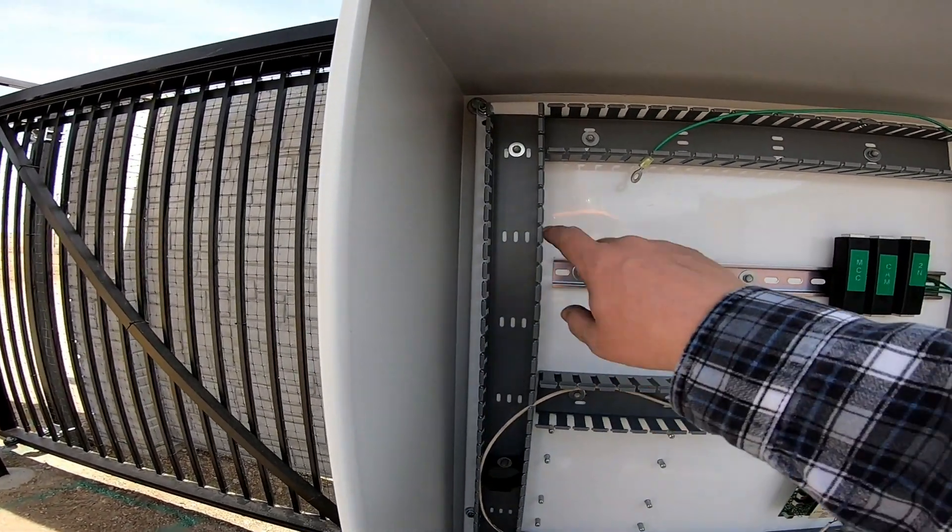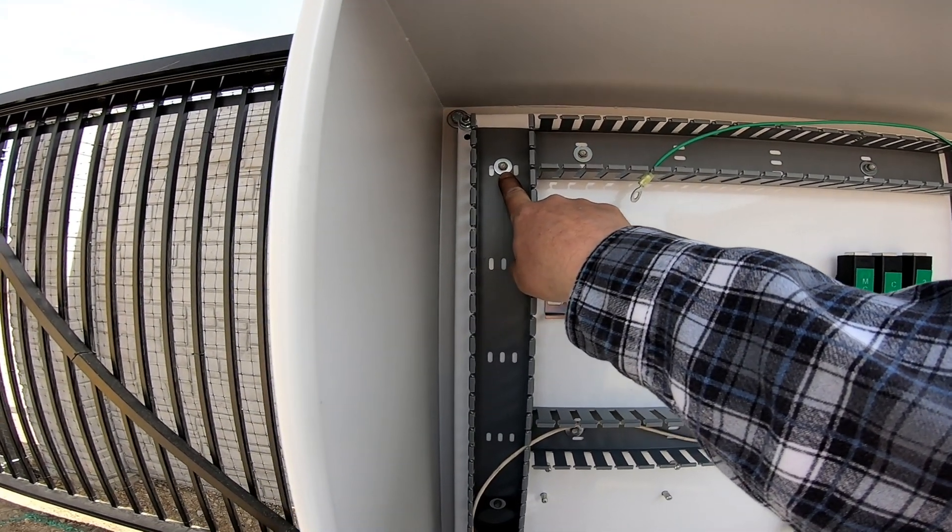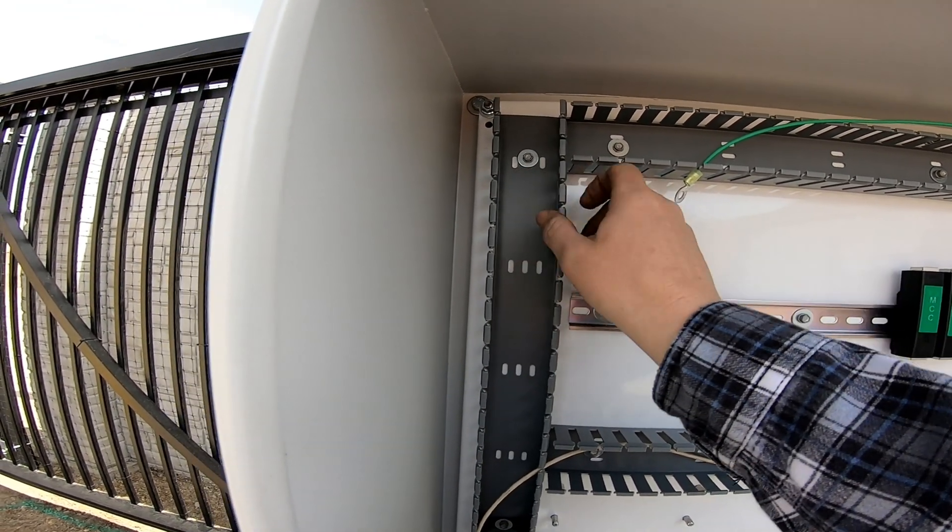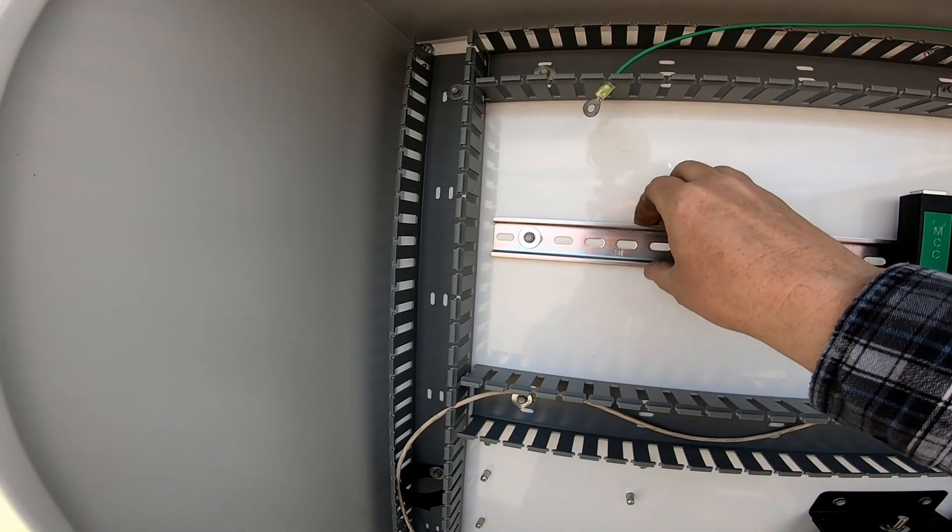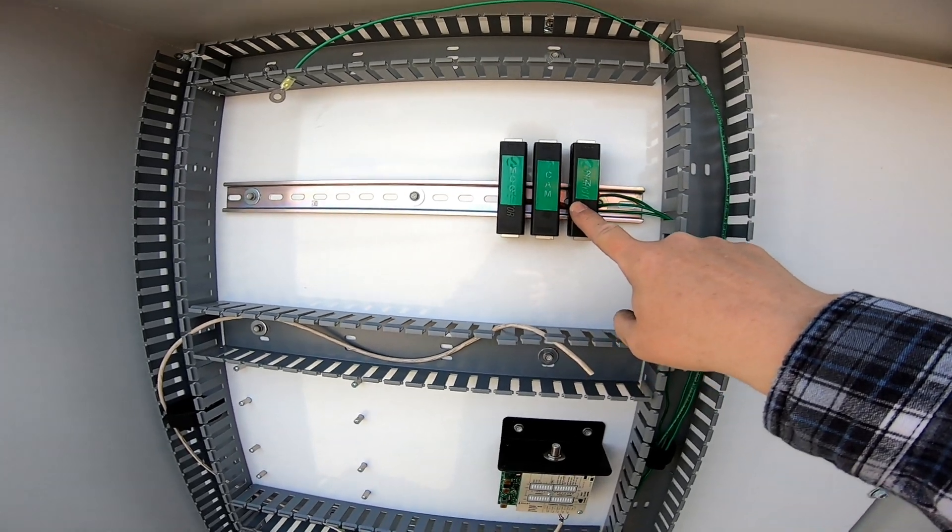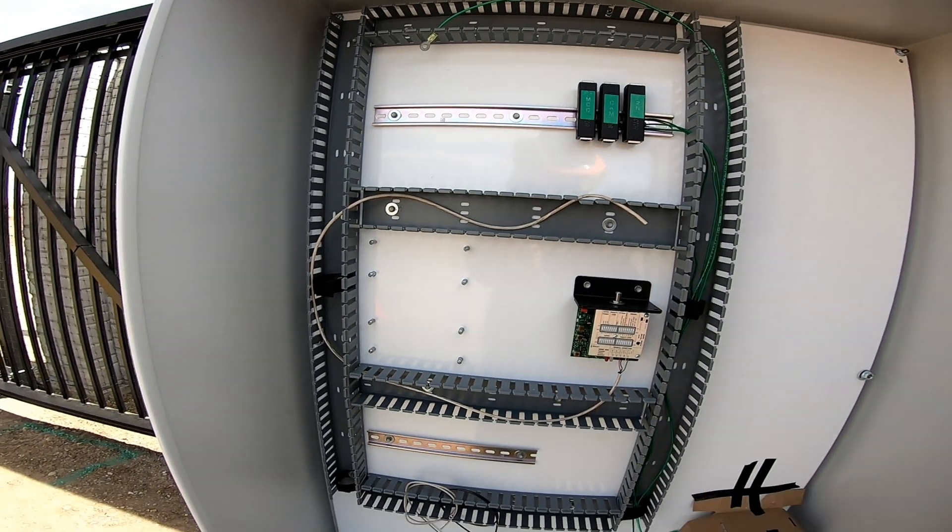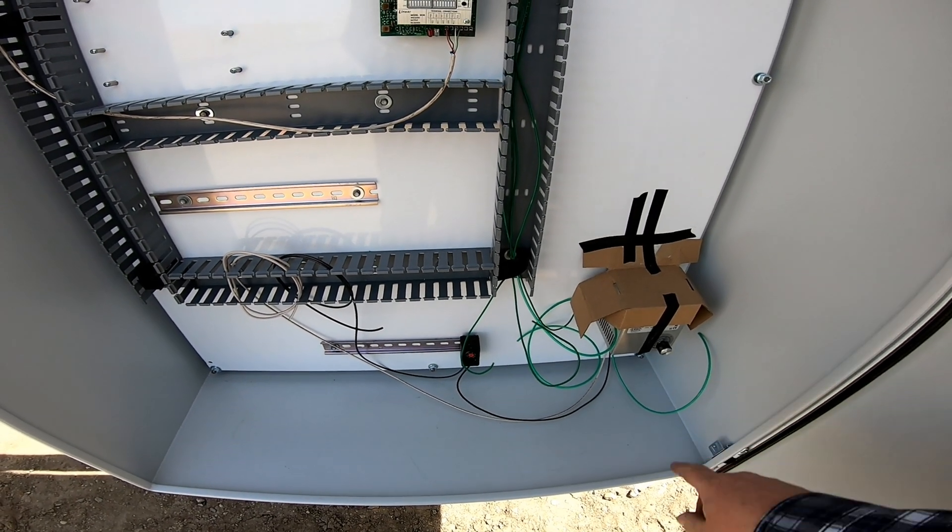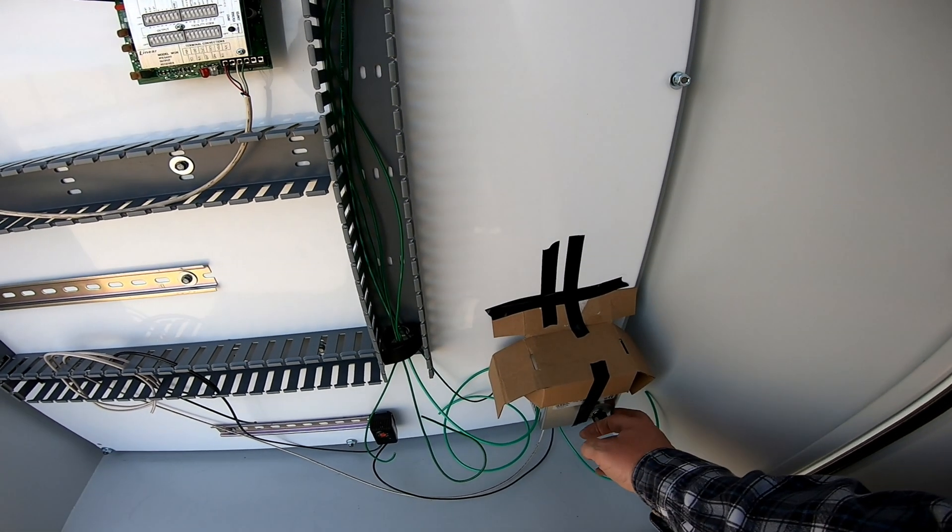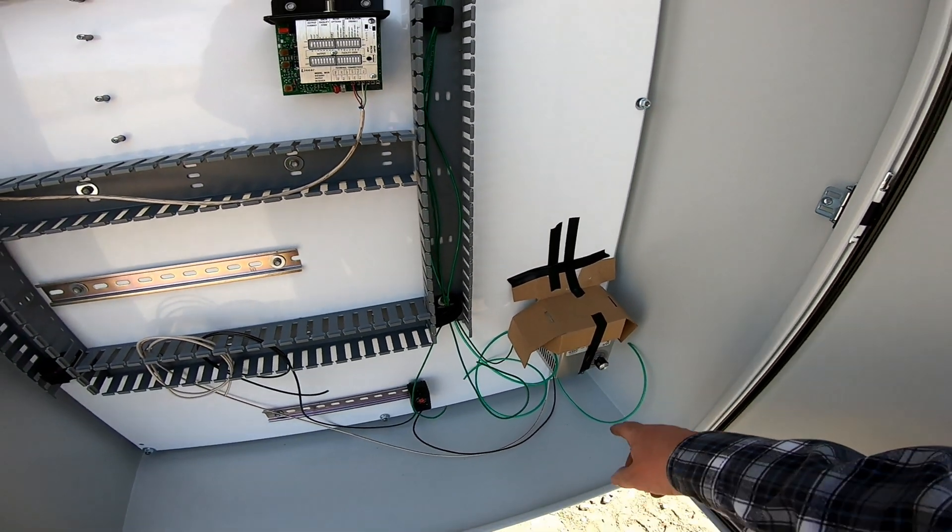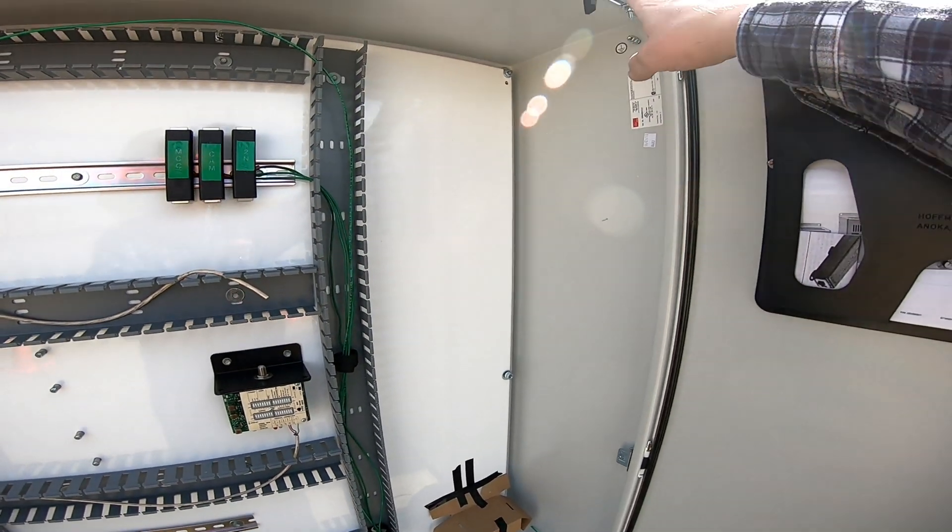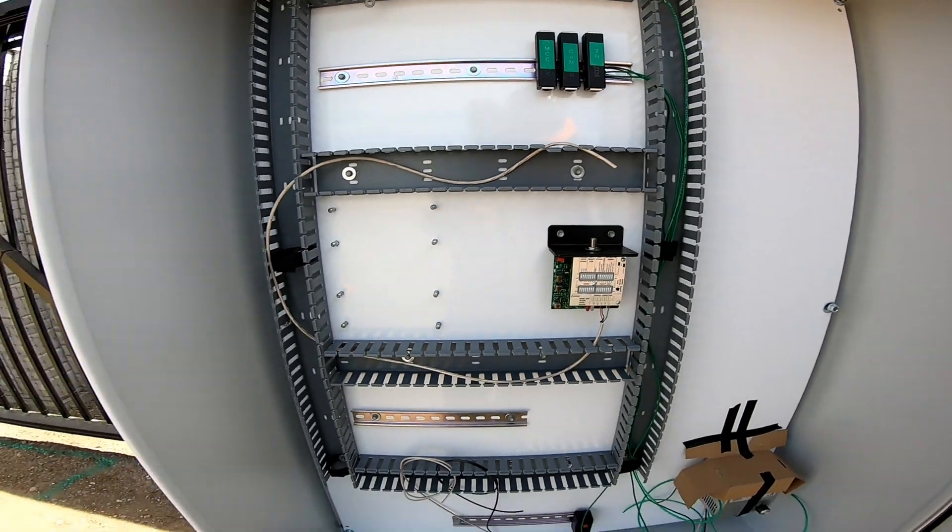Some of the key points: we use the proper screws that will go through this and won't pop off. We put some washers on here so it won't bow out. Same here. This is going to hold the network switch. We want it to be supportive. We grounded these. We pre-ran our wire. We've got a shutoff for our thermostat here. What happened a couple times years ago is you would think this thermostat would fail safe, but it doesn't. So this heater ran away and cooked some stuff in here. We've got our door stop up here so the door won't blow off.